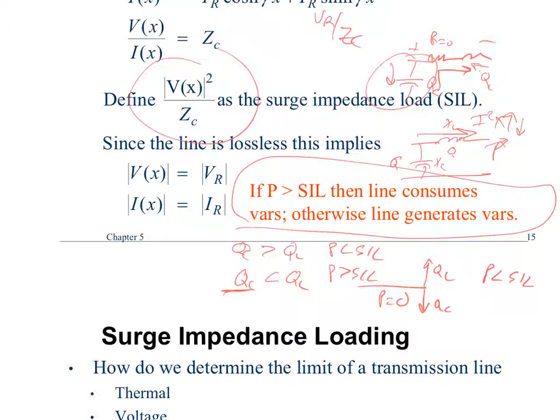All the time. Because at night, if the voltages get too high because you have all this reactive power, you start blowing things up, right? During the day, if the voltages are too low, then customers start complaining, saying they're getting some flicker and all that stuff. So, trick question, yes. So all the time, ISO New England down in Holyoke, they have to spend their entire time constantly monkeying with the outputs of generators and transmission lines to make sure voltages stay within tolerance.